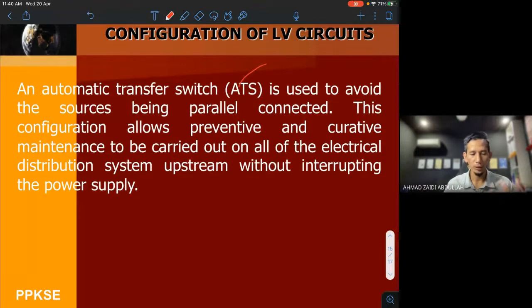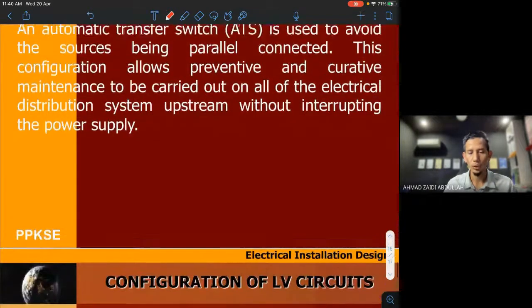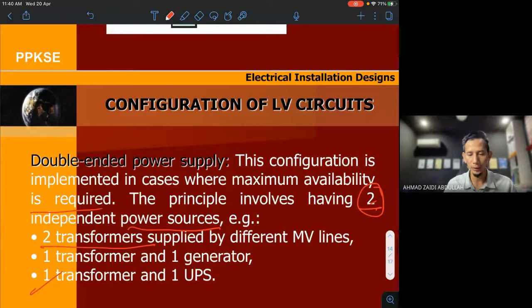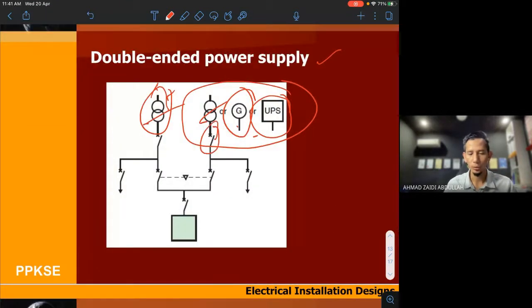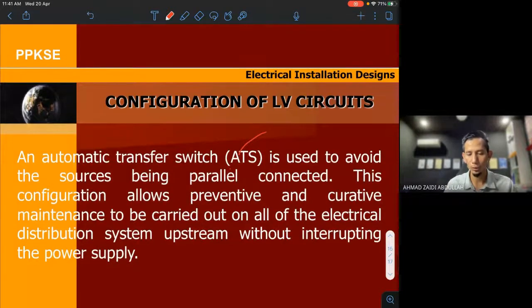ATS is used to avoid the sources being parallel connected. Okay, this configuration allows preventive and corrective maintenance to be carried out on all the electrical distribution. So normally you must use the ATS, the switching between here and here, it must use an ATS, automatic transfer switch. Okay, we don't want this load to take from both supplies at the same time. So normally the genset and transformer cannot work in parallel directly. It must have only one source. So that's why you need to have the ATS.